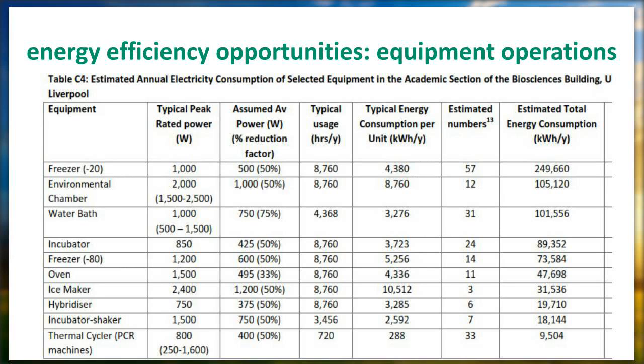And then they have approximated how much energy these things consume because, again, not a lot of information is known about that, as well as their typical usage per year, multiplied by the number of different types of equipment found in the laboratory, and you can see what the estimated total energy consumption is per year. The reason I wanted to show you this is just to demonstrate how this is one building in one academic institution in the UK, and they have 57 minus 20 freezers, which represent about 250,000 kilowatt hours per year of energy consumption, just from that alone.